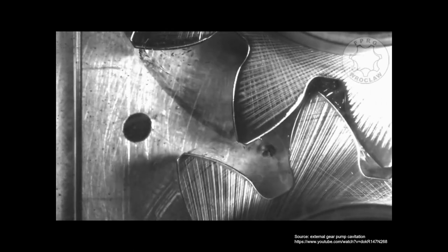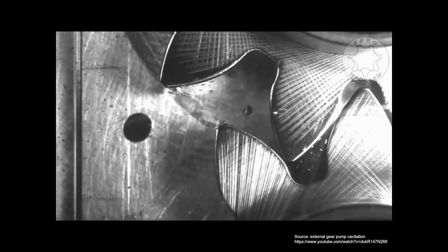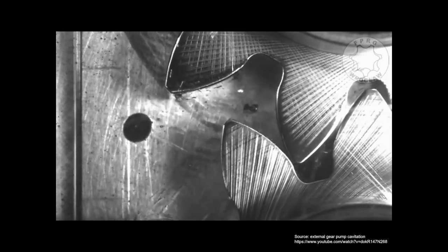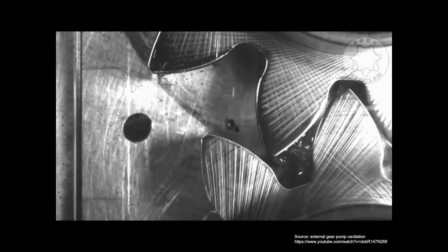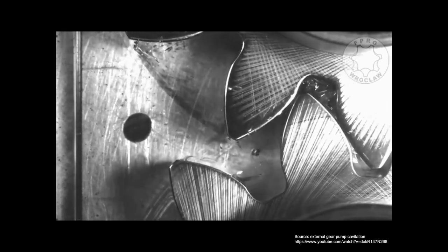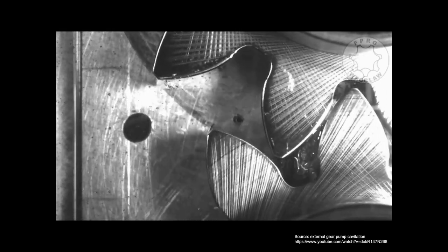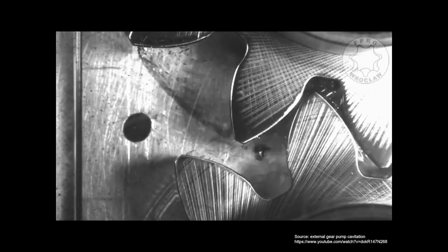This slide is a great representation of a demonstration of cavitation occurring in a rotary gear pump, which is typically used in a fuel oil system. Those little vortexes there are your fluid flashing. It's quite unique to be able to just see that discoloration with the swirl at the exit of the gears after they mesh. And it's pretty hard to believe that those little vortexes can actually eat away metal, huh? Just imagine they're running for 10 hours like this.